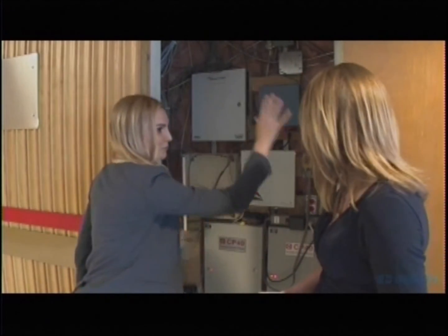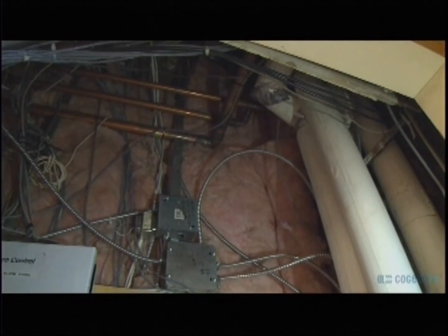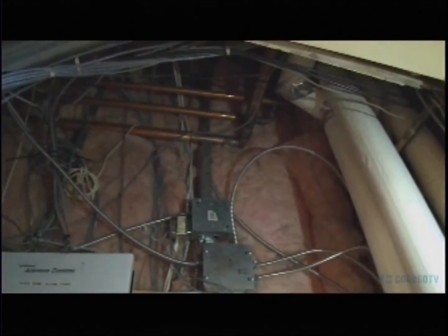There's also water coming through this closet and electrical services. So this is probably not a good mix for our digital hospital, and to add any more IT services in here would be a risk. If you're already using a housekeeping closet or a limited closet like this, there's really no more space to put any more IT services in here.